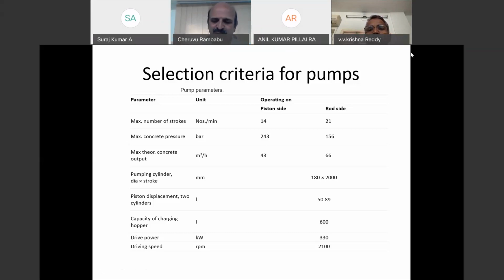When they start climbing heights, take the example of the Taipei Tower. From the 80th floor onwards, the output of this pump was coming as 8 cubic meters per hour, and after the 100th floor it dropped to about 6 cubic meters per hour. Though the theoretical rating is 66 cubic meters, as the height rises, the capacity of the pump comes down.